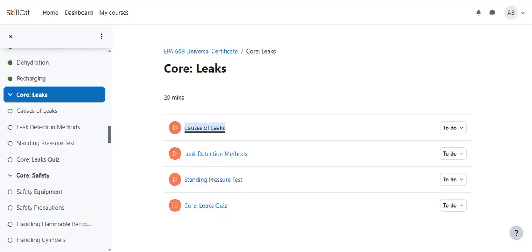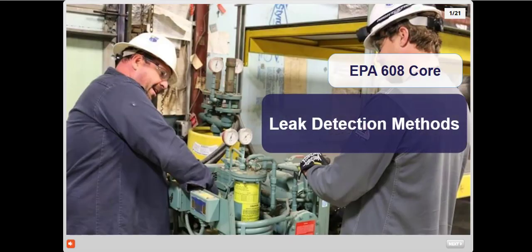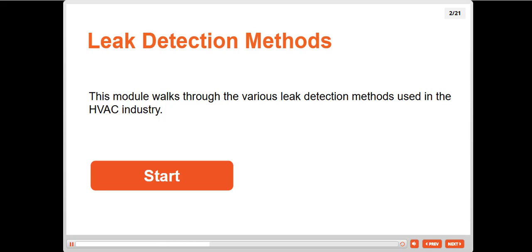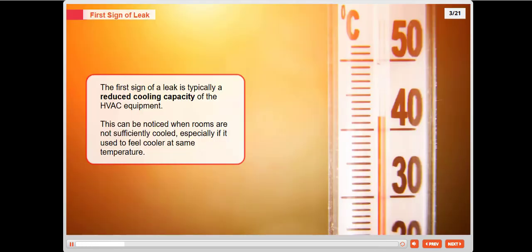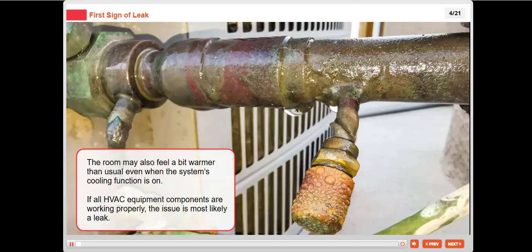Okay, now we will go to the next one, leak detection methods, how we detect the leakage. This module walks through the various leak detection methods used in the HVAC industry. The first sign of a leak is typically a reduced cooling capacity of the HVAC equipment. This can be noticed when rooms are not sufficiently cooled, especially if it used to feel cooler at the same temperature. The room may also feel a bit warmer than usual even when the system's cooling function is on. If all HVAC equipment components are working properly, the issue is most likely a leak.